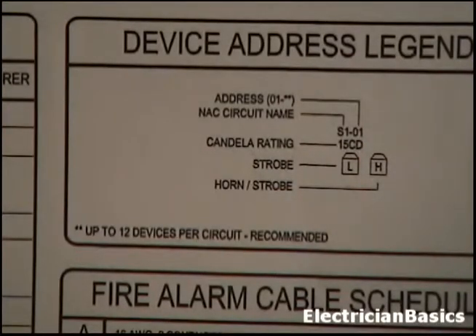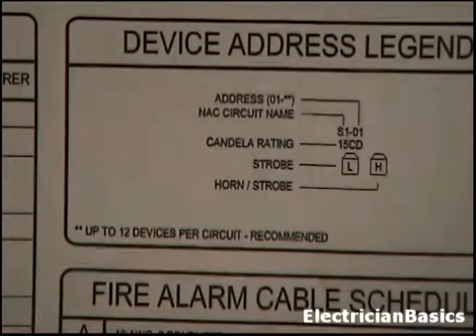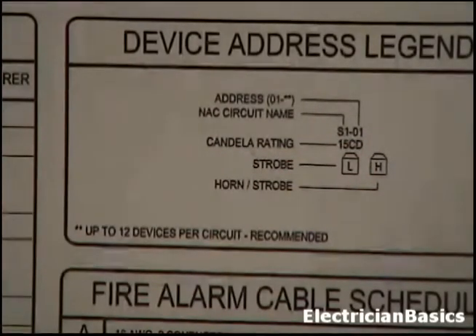And on a very, very large building that has many, many more circuits than this one, that's how they're going to tell, because it's in the computer and they say, well, the fire alarm goes off. And they say, well, where is the fire? Well, they'll be able to monitor that and say, okay, it's on circuit 1 and it's device 01. And then they'll have a computer which will kick up in the building. It will tell you what part of the building it's in. And if they're reading that and they say, okay, now device 2 goes off, and now device 3, they can tell that the fire is moving in that direction. So this helps the rescue people in their efforts, and it helps just to monitor the building and helps to keep it safer. And we'll cover these numbers a little bit more, but again, we just want to point out that this would be circuit 1 and the address is 01 or device 1 on that circuit.